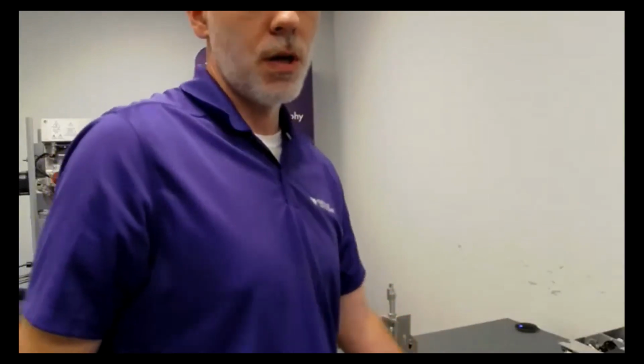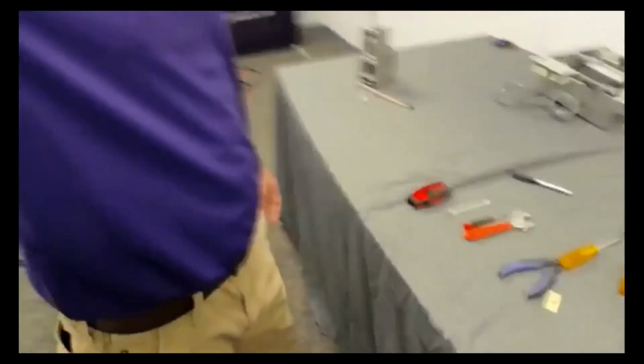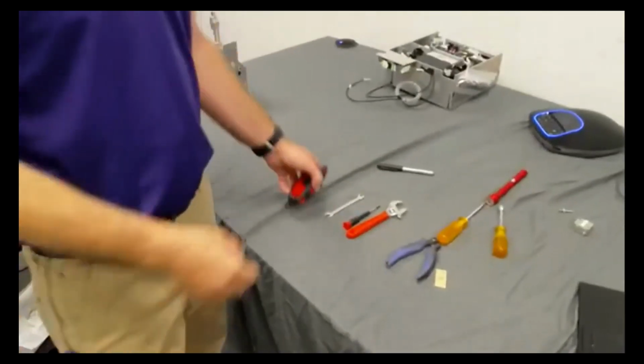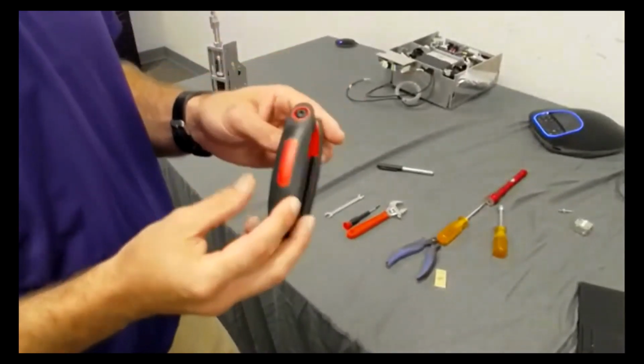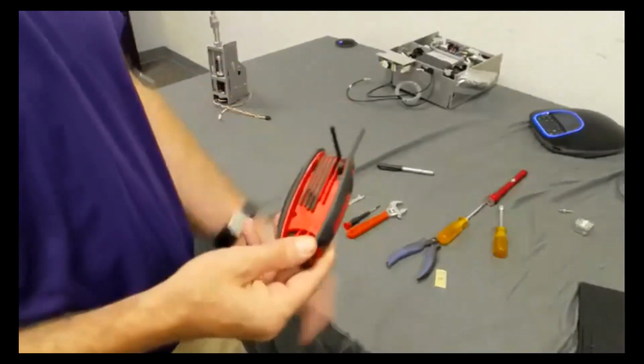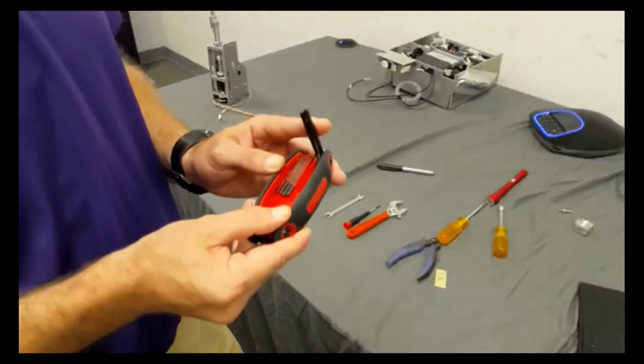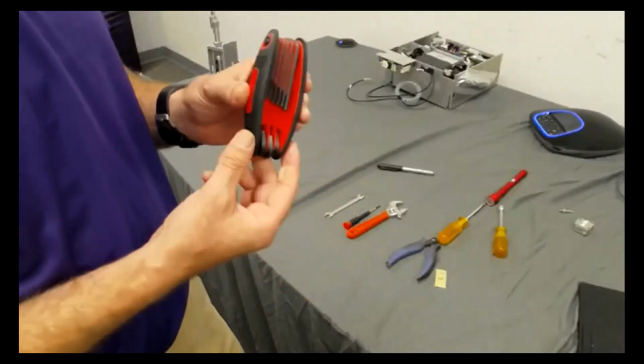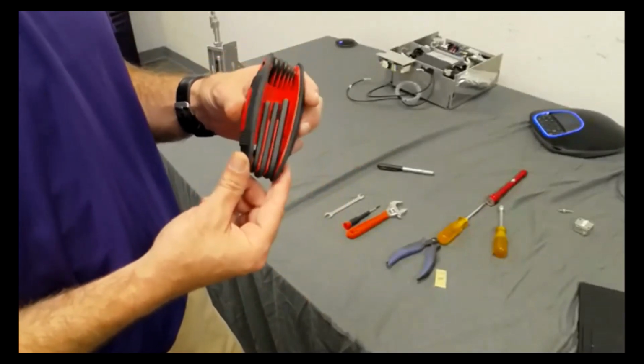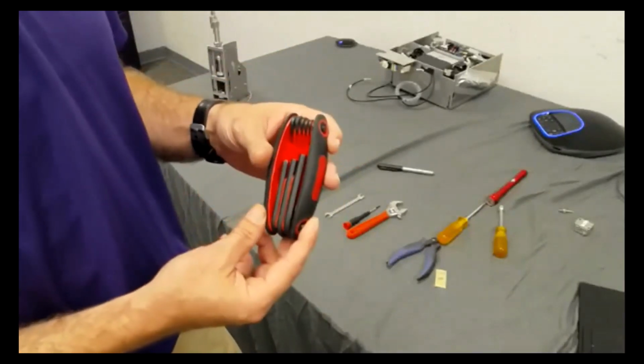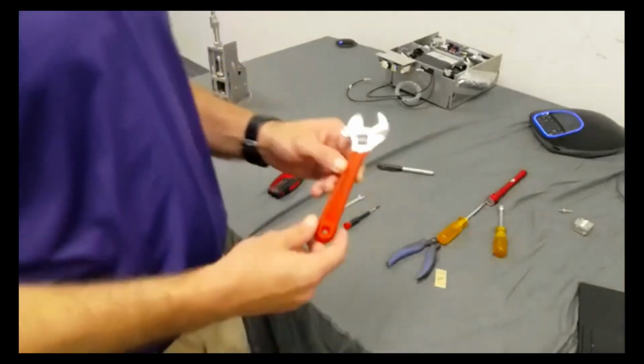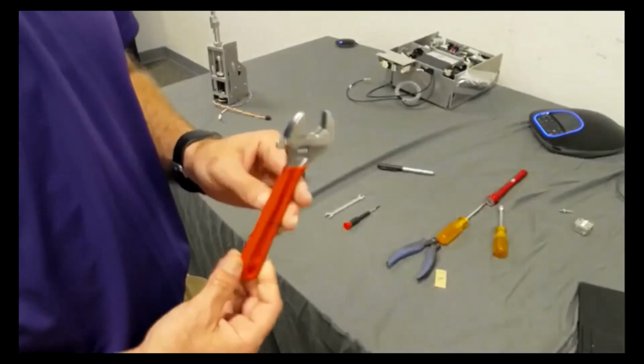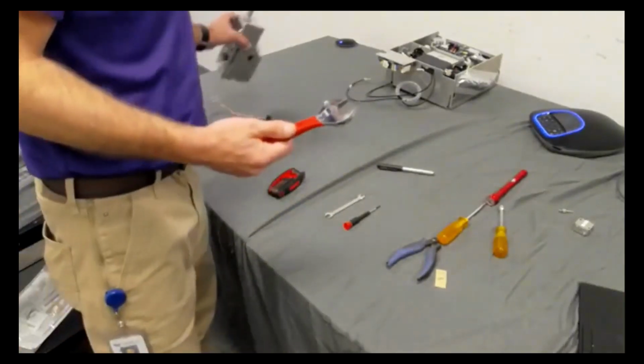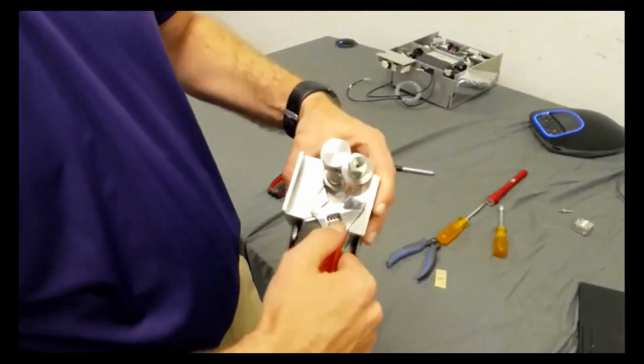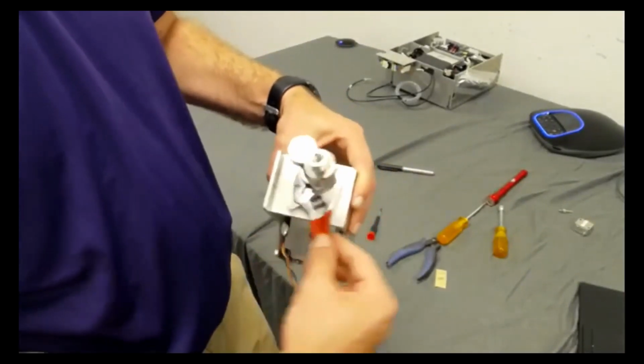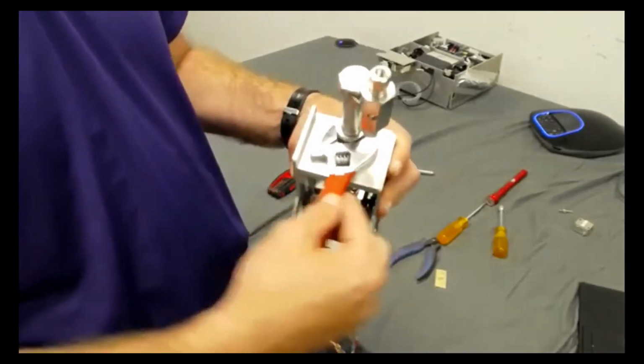Some of the tools I use, you want to have a standard Allen wrench set. This is the set that I like to use because I can't lose them. They're attached. But we're going to be using some of these for the actual PM. The check valve housings need to come off to replace that O-ring. Those are held on with Allen heads. You're going to need an adjustable crescent wrench, and it's got to be wide enough to go on the jam nut at the top of the pump here. It's got to be wide enough. Otherwise, you're wasting your time. Get a crescent wrench that's wide enough.